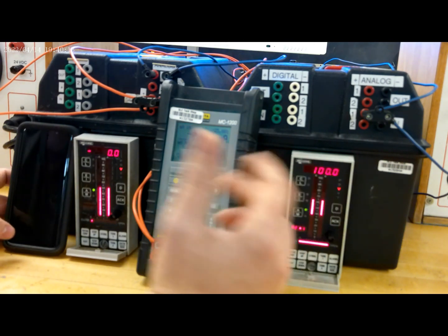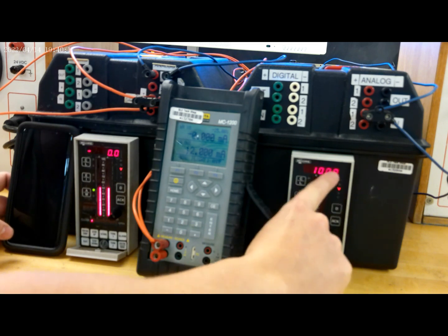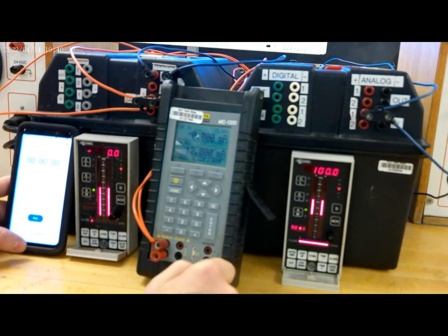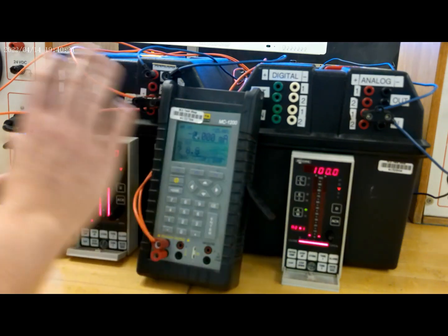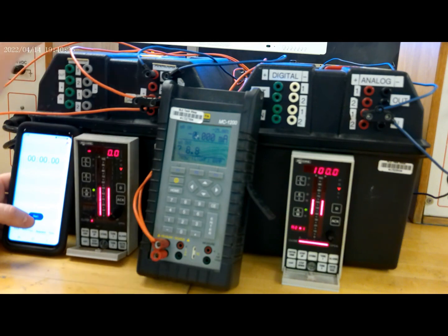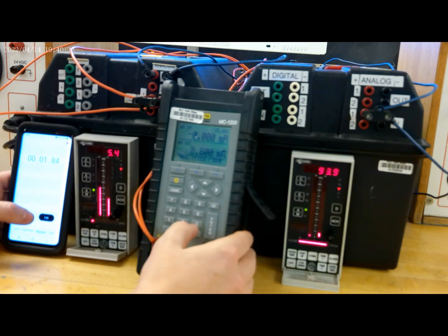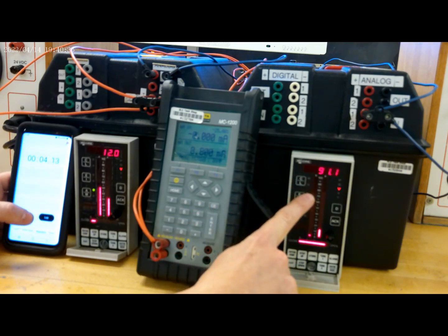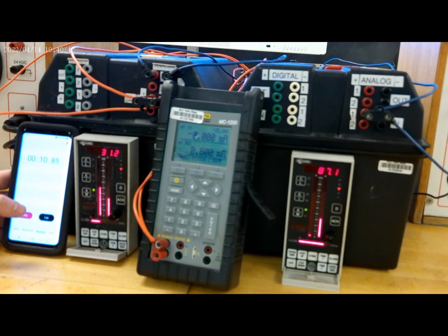So let's try that. We are in automatic mode. Our valve is at 100%. I've got my timer ready. I'm going to create the air to the first controller, which is going to give us the ramp rate. I'm going to try to hit them at the same time. So we notice that it dropped down almost instantaneously to 91. Now, I know it wasn't exactly instantaneous, but it was very close.